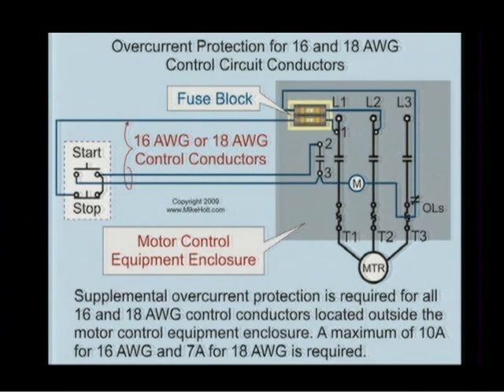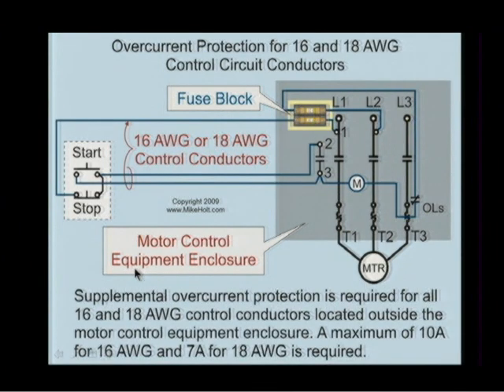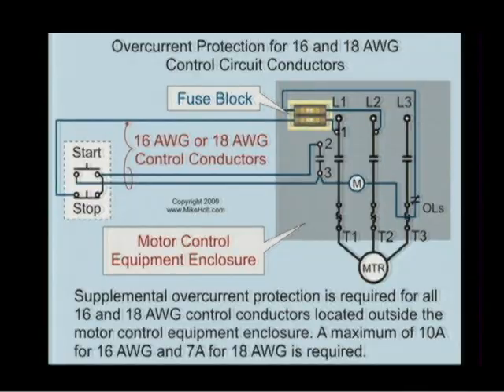Is it common to make a tap and not have direct overcurrent protection for the control wires extending beyond the enclosure? If you're going to do that, you're pretty much limited to some pretty small circuits, right? A 45 amp protection device, a 60 amp, that's for 14, 60 amp is going to be for 12. You're probably not going to be running 10 gauge control. So more than likely, in some very small circuits, you'd be able to make your connection, make a tap, and take off. But if we're going to get larger than smaller circuits, you need to provide overcurrent protection for those conductors. Then we'd have to go with a fuse block and provide protection. That's if there's no transformer involved.